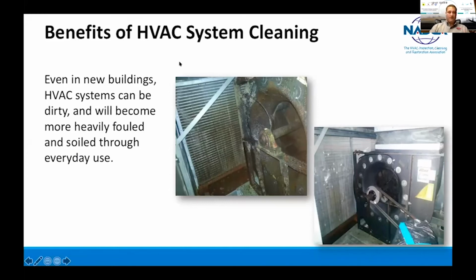Even in new buildings, whether it's a new building or an older building, systems become dirty. They go through a construction process, and not all construction has the engineering controls to be able to keep the building clean during the build out. And these HVAC systems, when they become dirty, they soil the system. And then everyday use, as we bring in fresh air, and as we're trying to understand especially more about COVID-19, we are reintroducing things into buildings that are going to have dramatic impacts on the HVAC system.